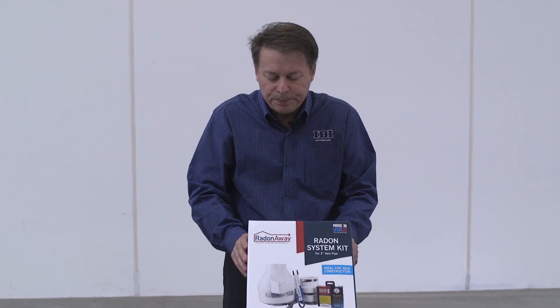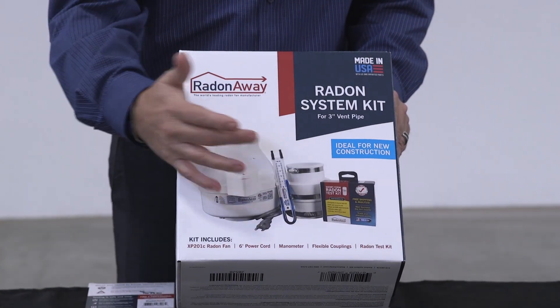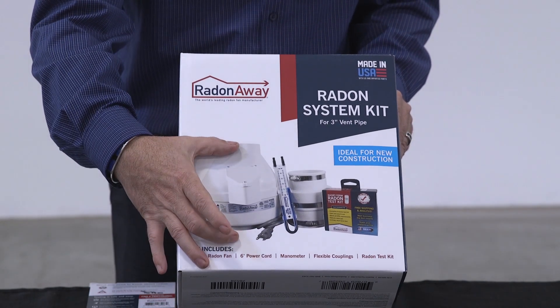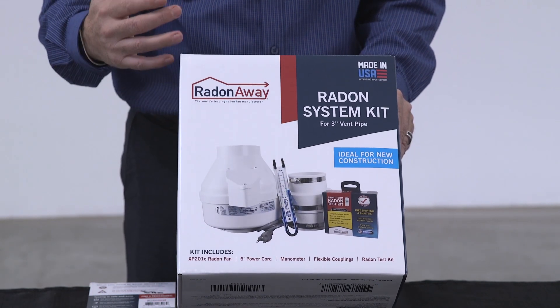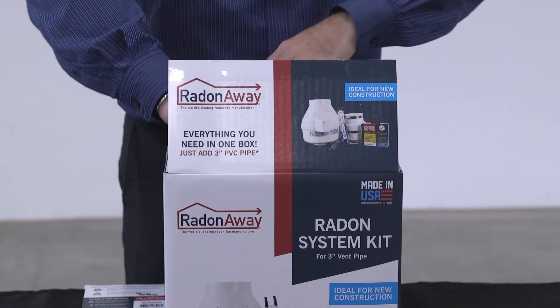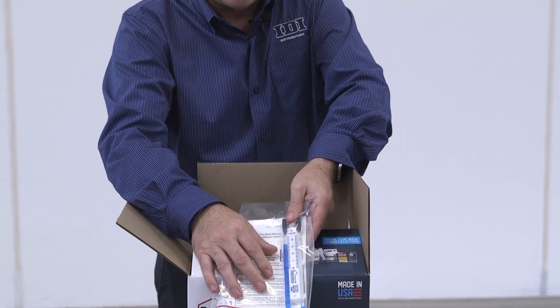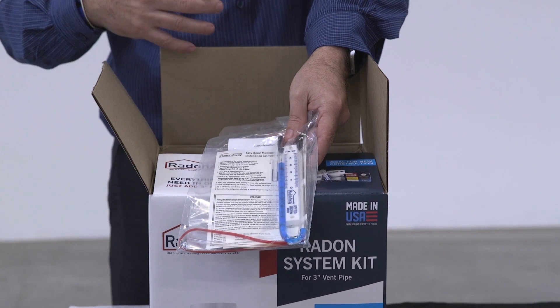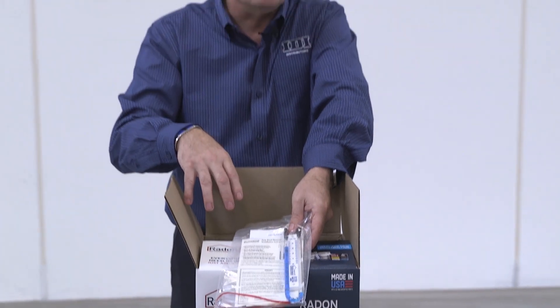These kits are very inexpensive, but what comes in them is what I want to show you. You're going to get another test kit, but in addition to that you get the couplers that connect to the pipe that you'd get at a common hardware store. It comes with the radon mitigation fan, the manometer, and power cord. The manometer tells you whether it's working — it's a simple U-shaped tube. This liquid is going to come around and start coming up to show you how much water column there is, which is created by the vacuum from the fan.